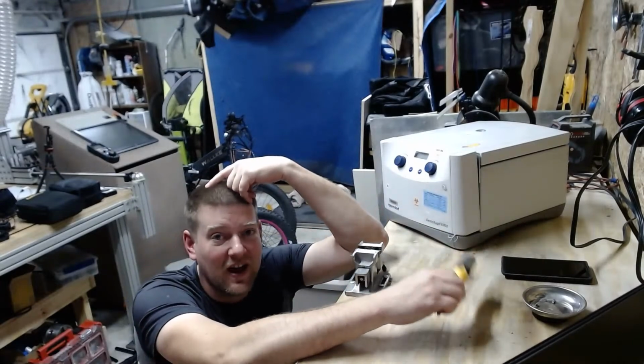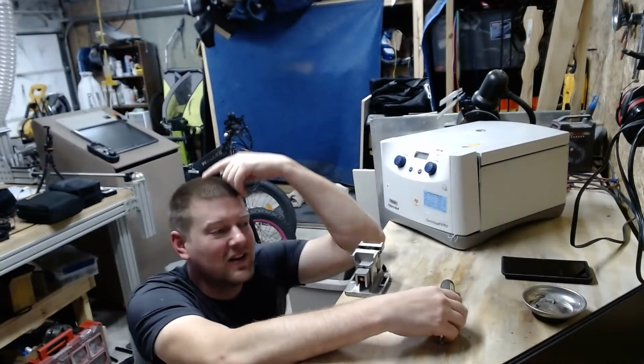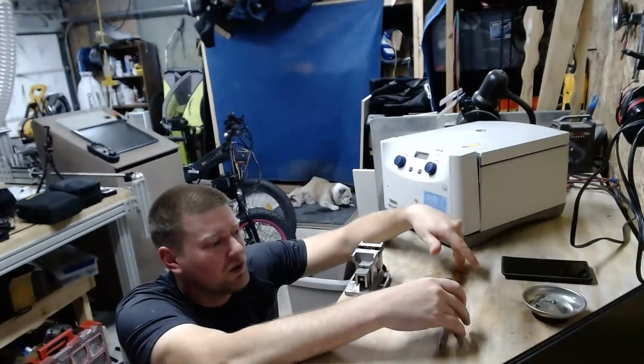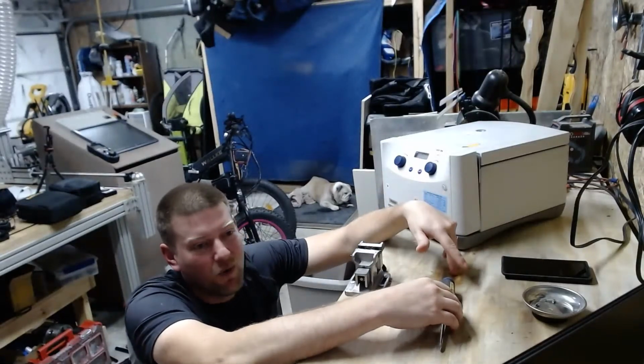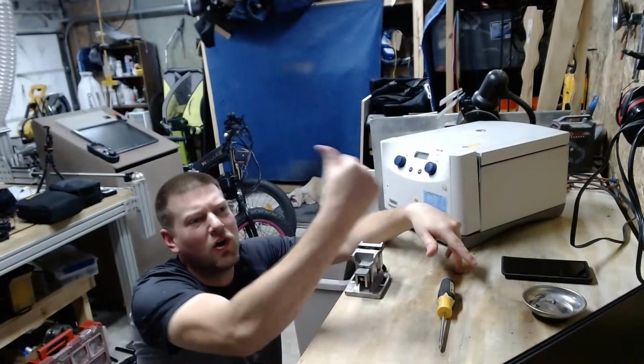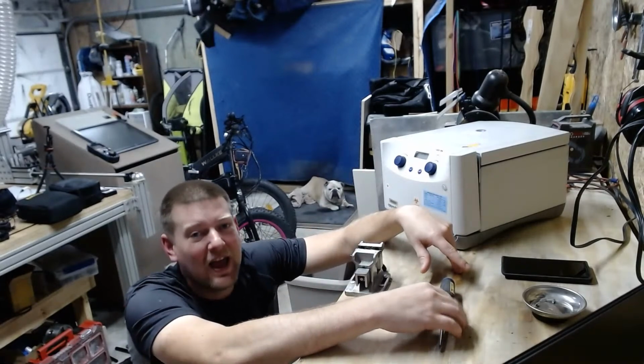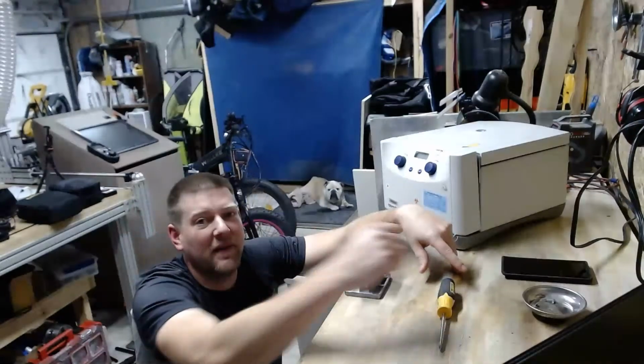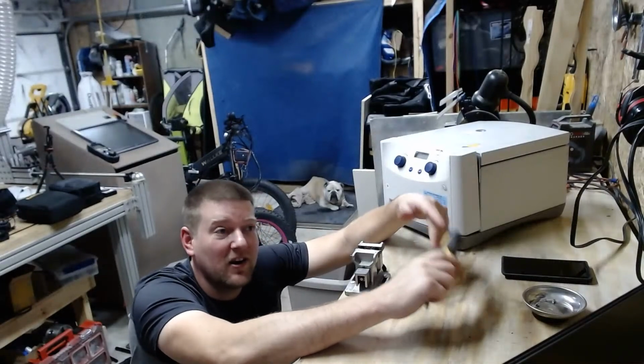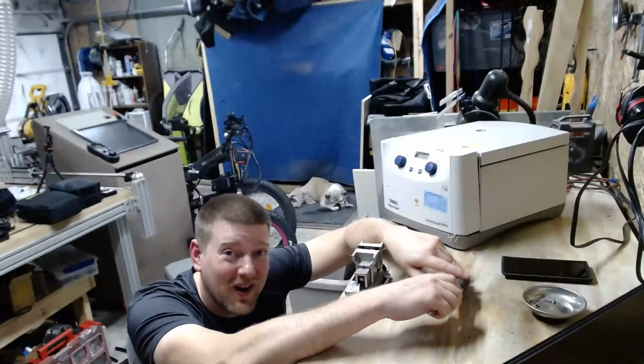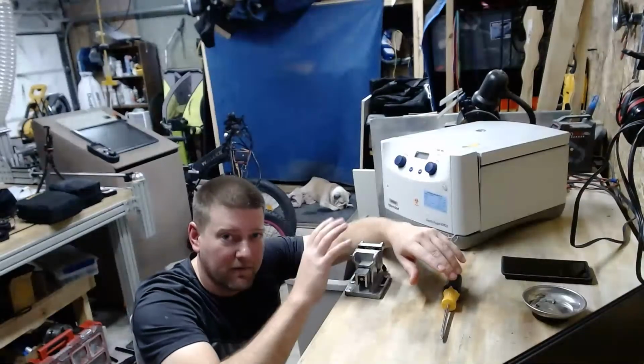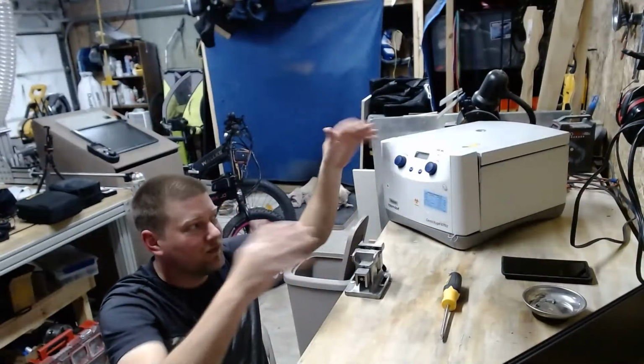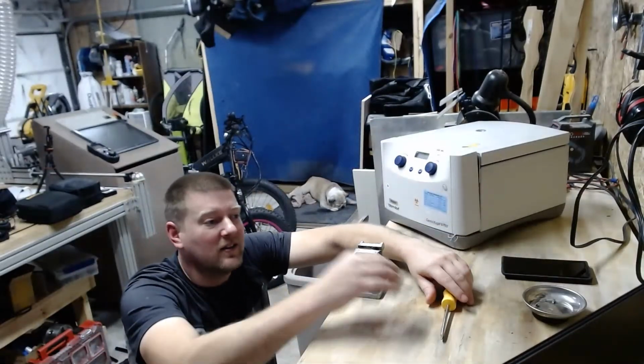If you can imagine how that could go wrong, let's say you start testing an ESU at 5 or 10 watts, then go all the way up to 300 watts, then shut it off and go do something else. They turn it on expecting a lower setting, and instead you're shooting 300 watts on a device that's been in their room for years, maybe. They just walk up to it, press a button, and walk away.